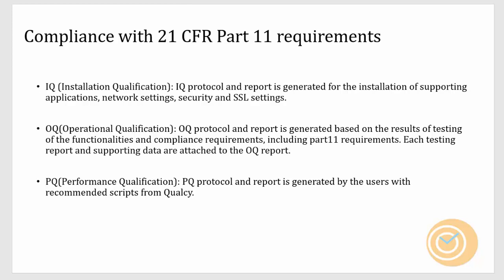And you would need to create OQ protocols and the OQ report. The OQ protocol would cover all the test cases that you are planning to do. And once you complete your testing, you can attach your testing results and the screenshots to the OQ protocol. So that will be your OQ report.